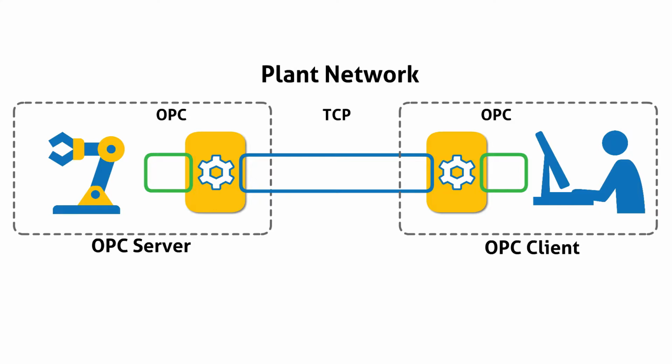It keeps all OPC communication local to the server and client machines, and then mirrors the data across the network. When there's a problem, the clients can keep working with the last known values from the DataHub on their local system. When the network comes back up, both DataHubs synchronize automatically. The clients never time out or freeze, waiting for an answer.